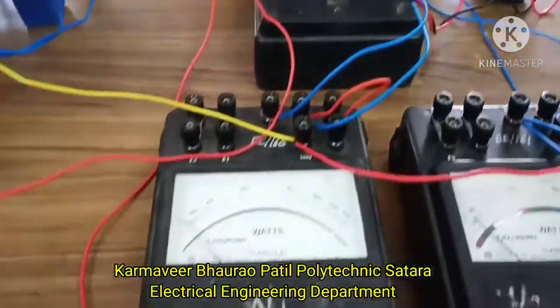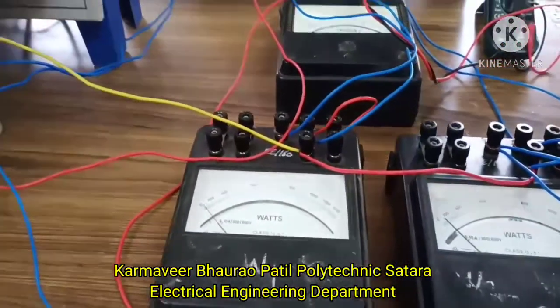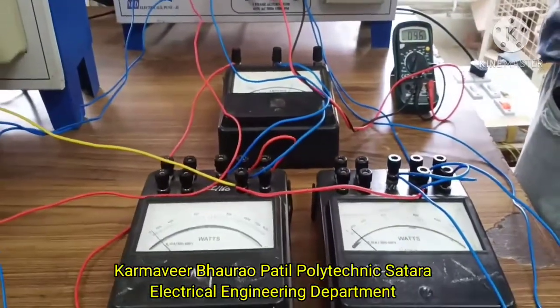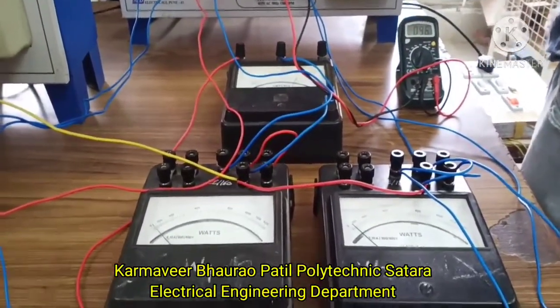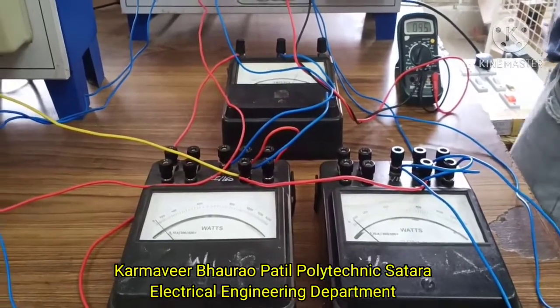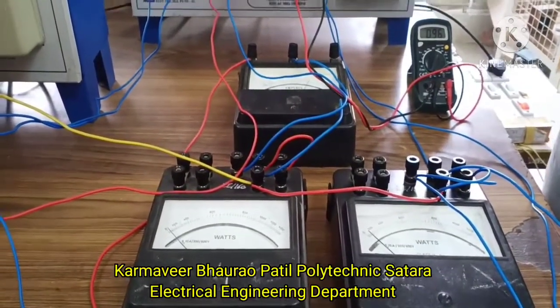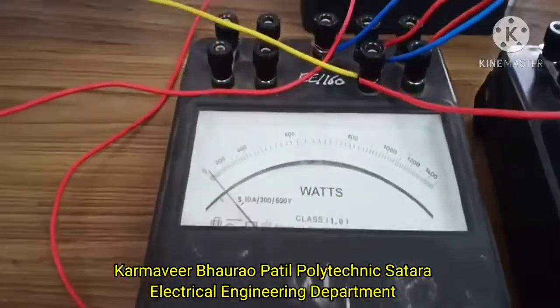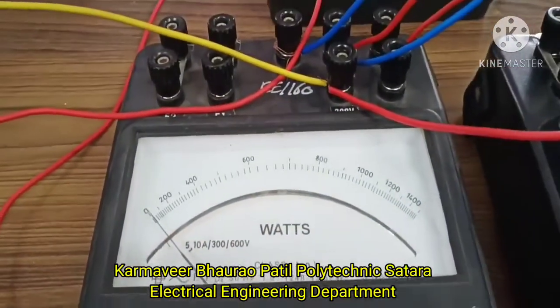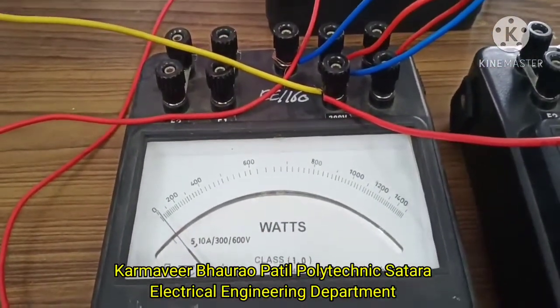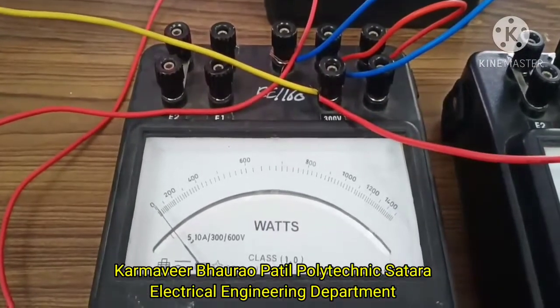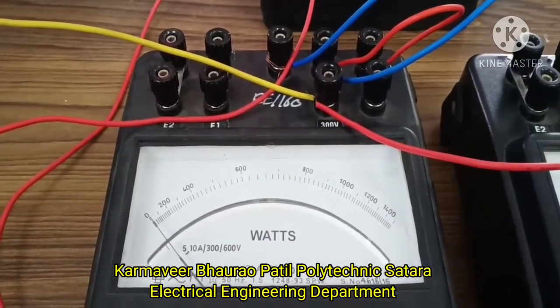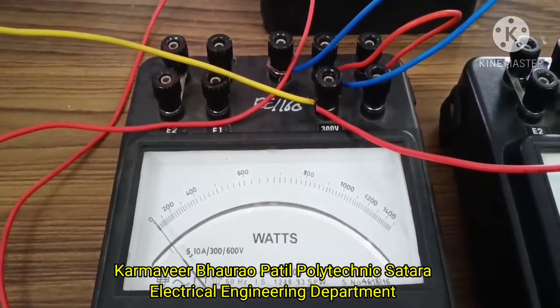And we will block the rotor. Voltage is 96, that is the reduced voltage we have applied for this block rotor test, and we have to block the rotor by holding it by hand. We also have to measure the power, that is the short circuit power. So this is our W1.